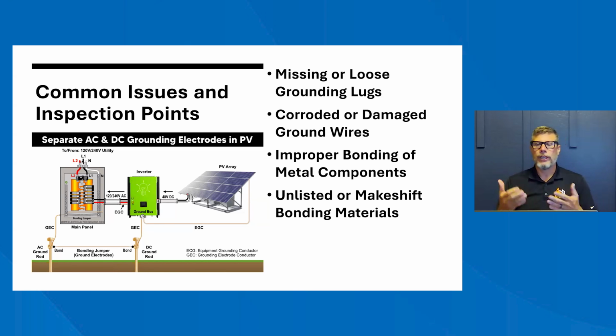When you're looking at the PV system, the grounding system is usually attached to the racking system. So where the whole frame of the array where the modules sit, you'll see the ground attached to it. If you have a series of arrays like you see here, that's a series of 3 arrays. Those will all be attached by a grounding or a bonding wire. There'll be a ground and a bond for each one. You want to look for corrosion or damage to the ground wires. Sometimes you'll see the ground wire goes directly to the ground. It doesn't actually go to the panel. It's very rare that you'll see that, but it does occur.